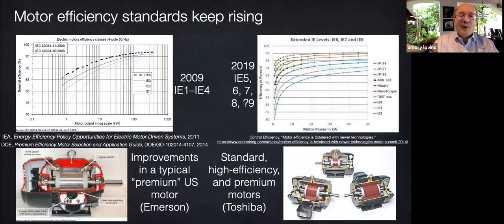that saving keeps rising. Most old motors, especially those with no or illegible nameplates, are standard efficiency, IE1 or worse. That's the lowest gray curve at the upper left graph. Current standards are at least the top solid line, achieved by the features shown on the lower left in a design transition illustrated at the lower right. Minimal good practice is the top dashed line at the upper left.